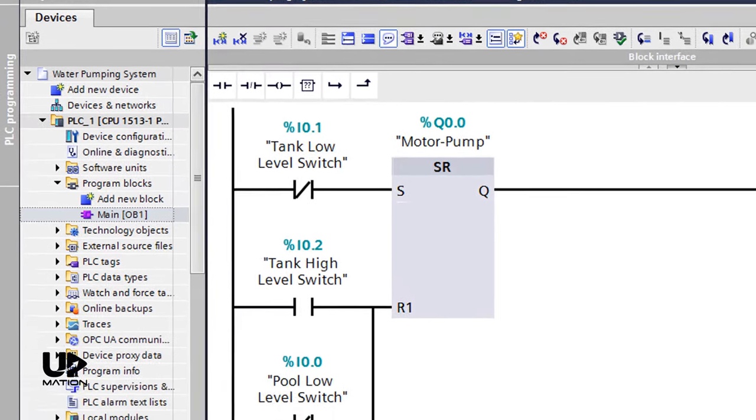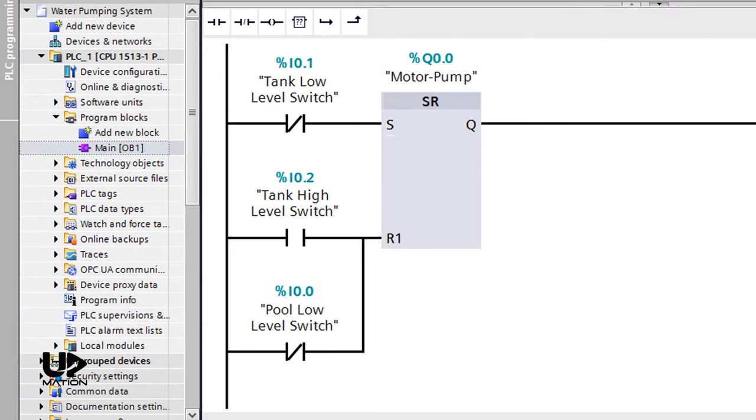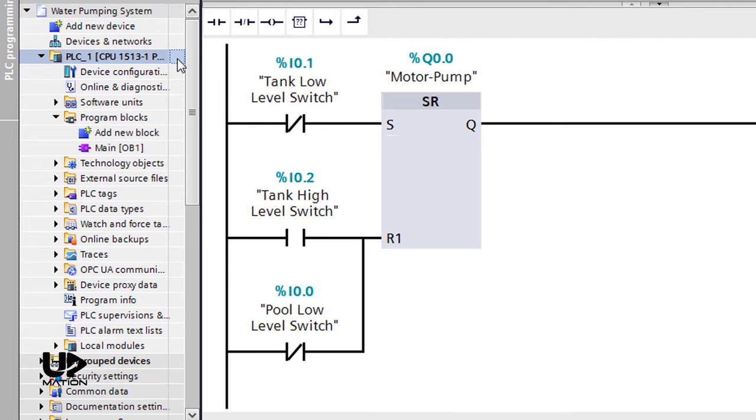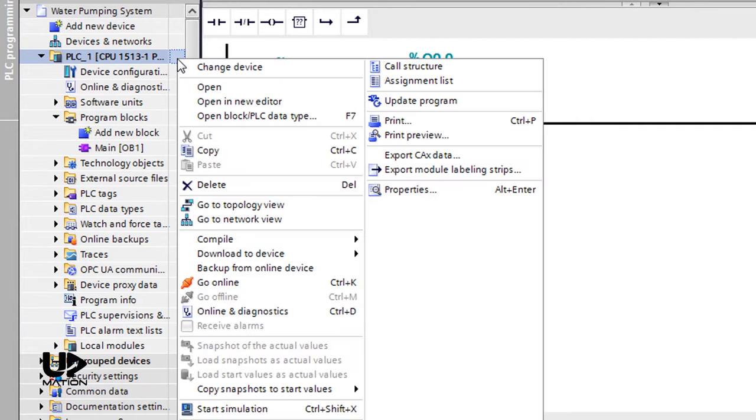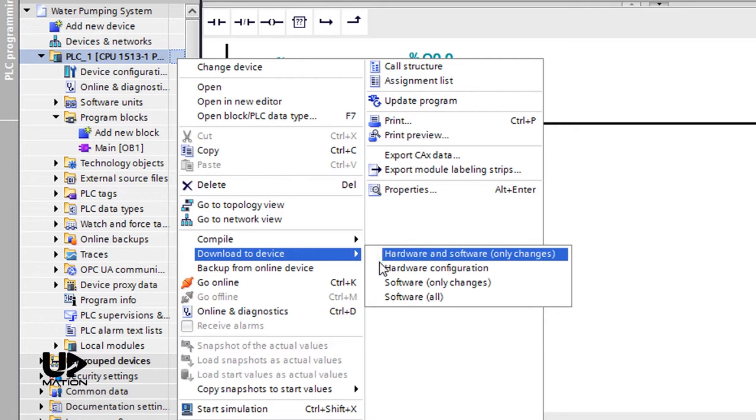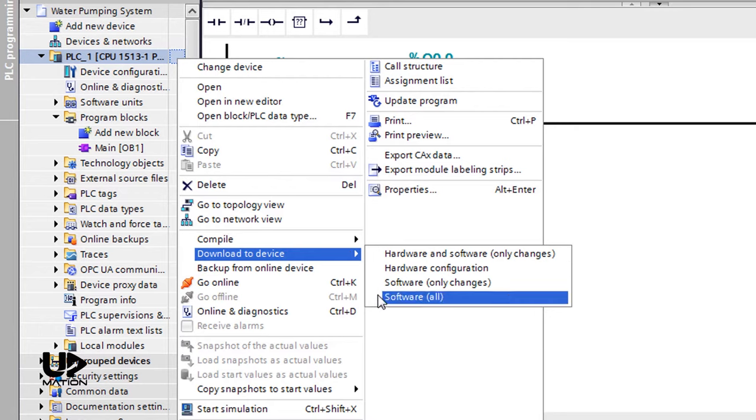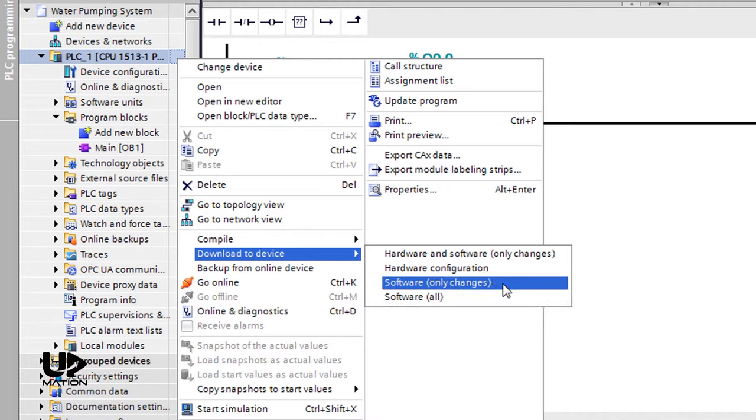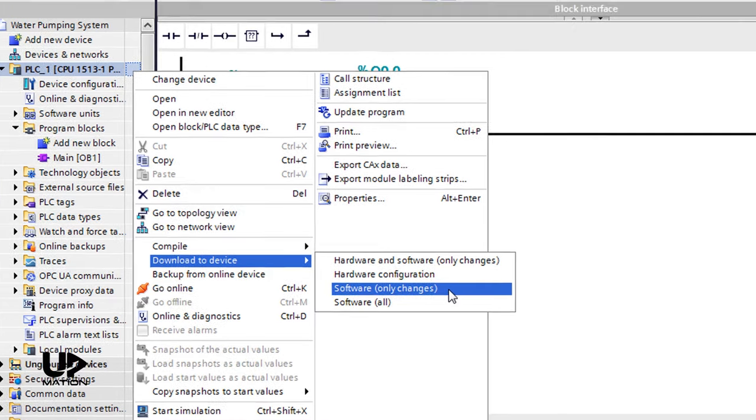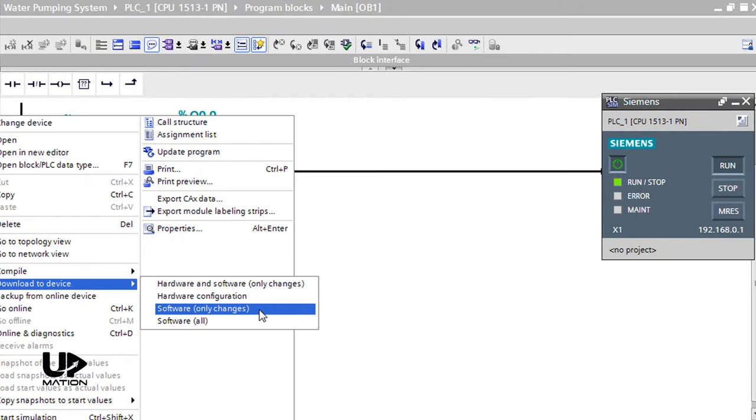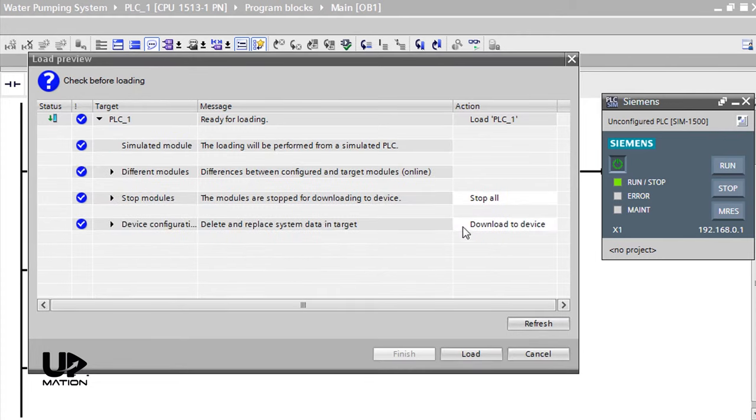But a more common method for downloading the software or hardware to the PLC, specifically when the process is running, is to simply choose the PLC and right-click on that. In the download to device menu, there are four options. If you have made some changes to the software and you only want to apply those changes, you should choose software, only changes. In this way, you will let the CPU stay in the run mode. This is especially useful when the process is running and we don't want to interrupt the process by stopping the CPU. The other options will stop the CPU, by the way.